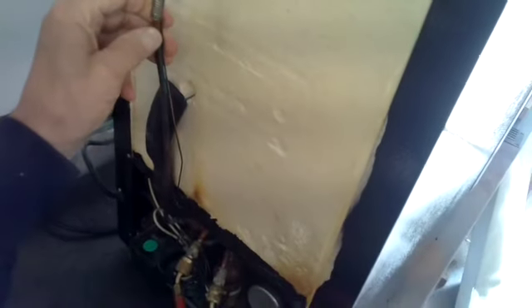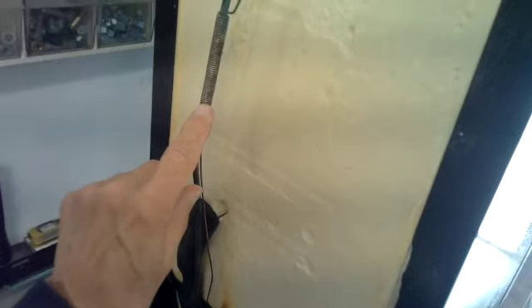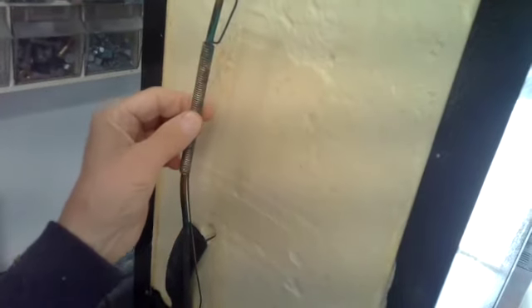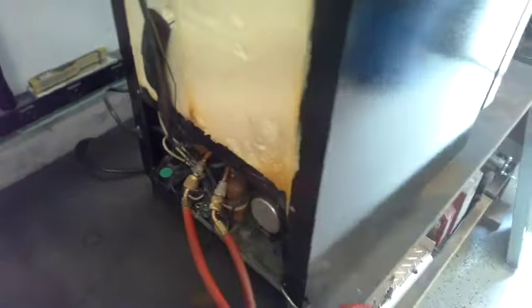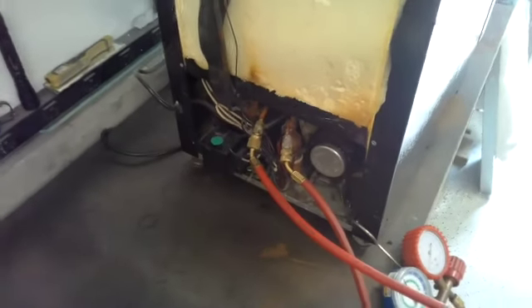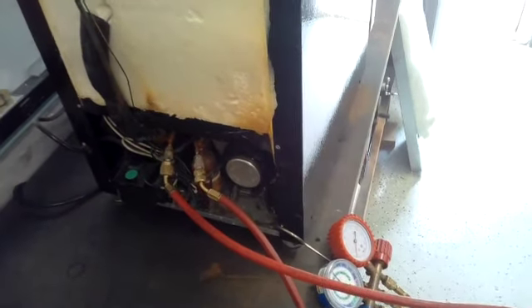The problem is that these parts are no longer available. We can't get the evaporator plate. We can't get the heat exchanger. And as I showed you in the video, we were picking up traces of leak in this area of the heat exchanger. So there is only one option left to do. I'm not sure if the customer is going to want to spend the money. It's a big job, but maybe for the purpose of just showing that it could be done, we may do it anyway and then install this U-line evaporator, because the heat exchanger is already included in this plate. And I'll show you.